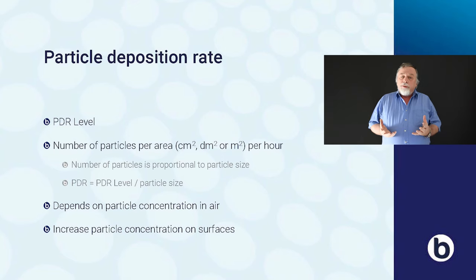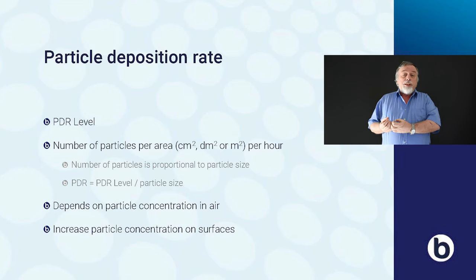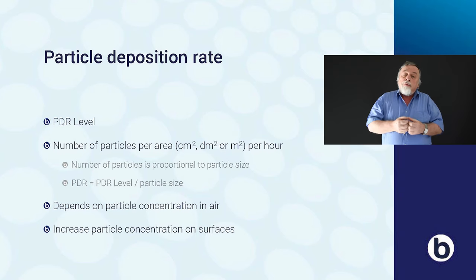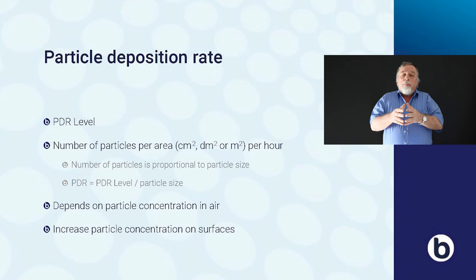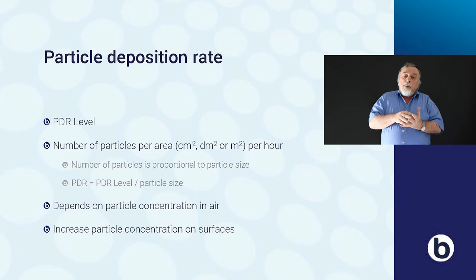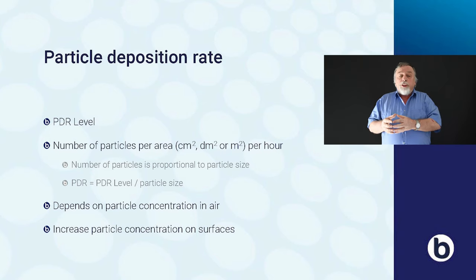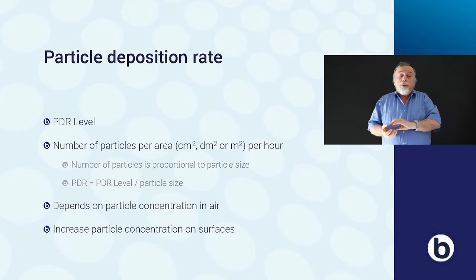Particle deposition rate is the number of particles larger than a particular size d (in micrometers) per area per hour. A particle deposition rate level is independent of particle size and gives a general level of particle deposition in the clean room, expressed in number of particles per area — in square centimeters, square decimeters, or square meters — per hour. The number of particles that deposit is proportional to the particle size. The particle deposition rate can be found by dividing the particle deposition rate level by the particle size d.